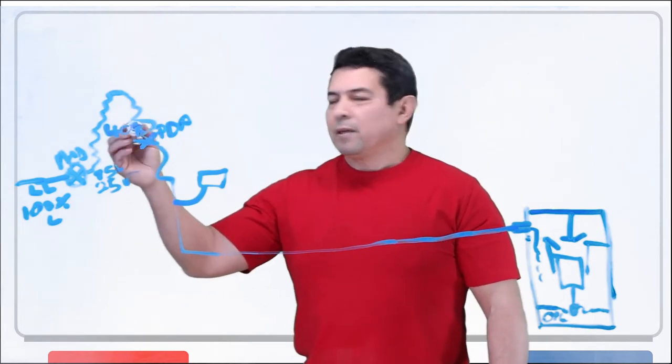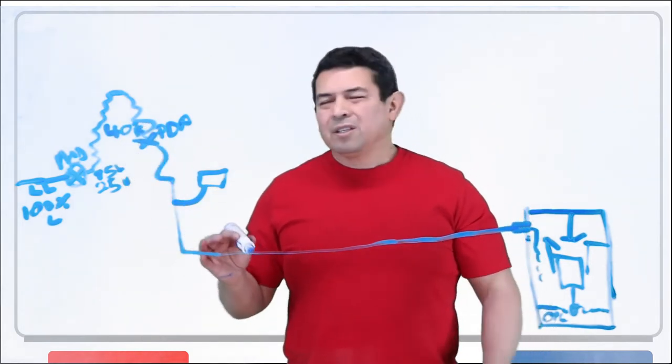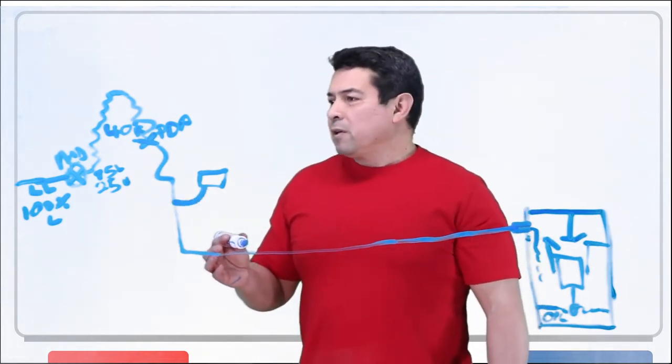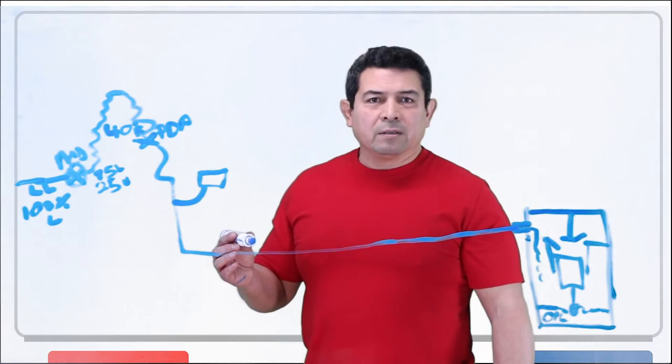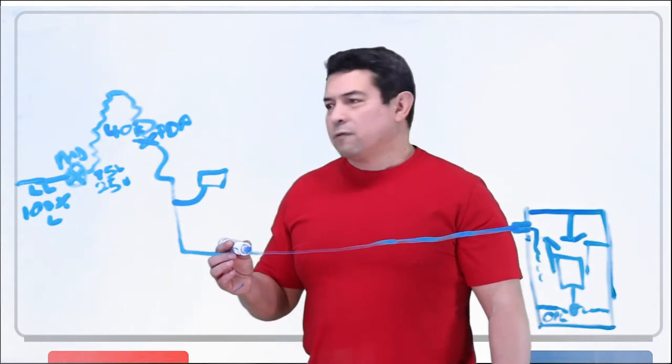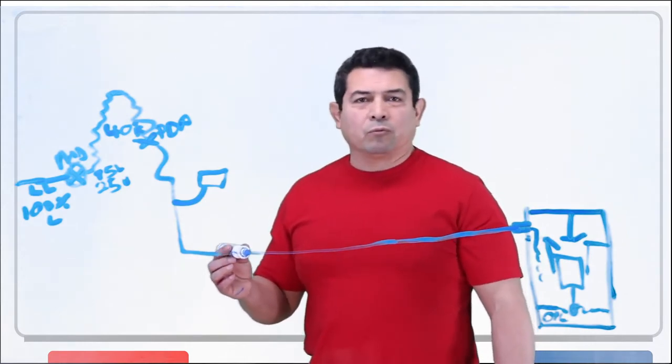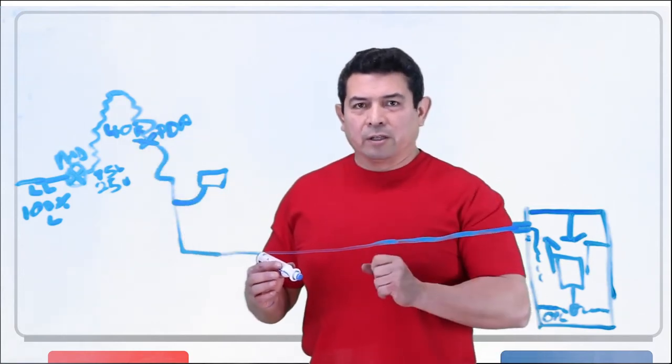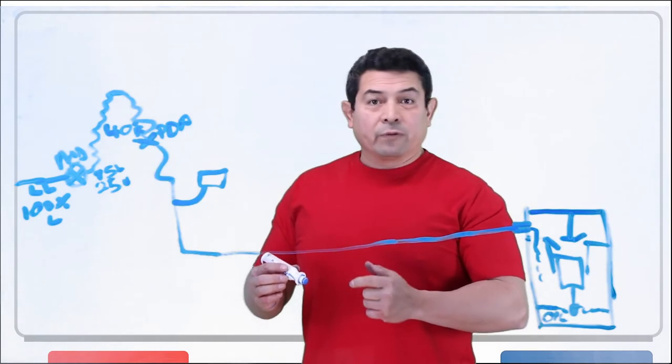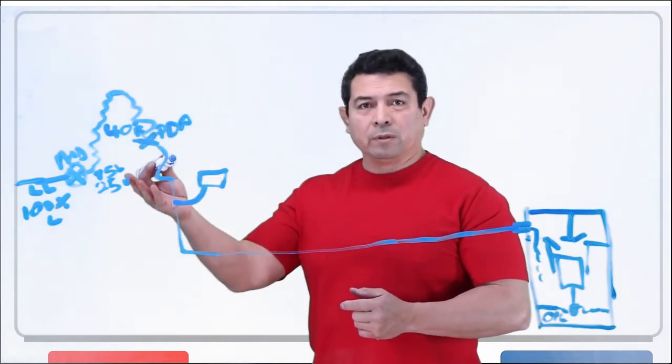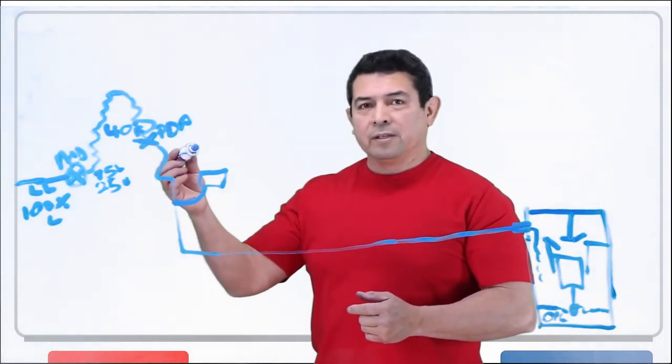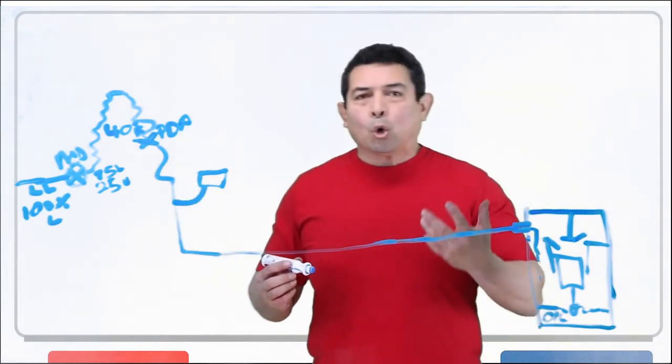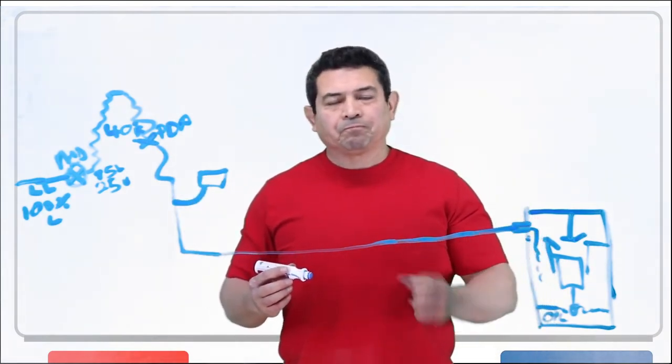Now if this is R22, typically we want 40. If this is, let's say, 407C, 40 degrees. If it's 410A, whichever, we still want that to be 40 degrees if it is an air conditioning system. If it is a refrigerator, of course, it's going to be lower. And if it is in a freezer, it's going to be much, much lower. It's going to be down to zero or below zero degrees.